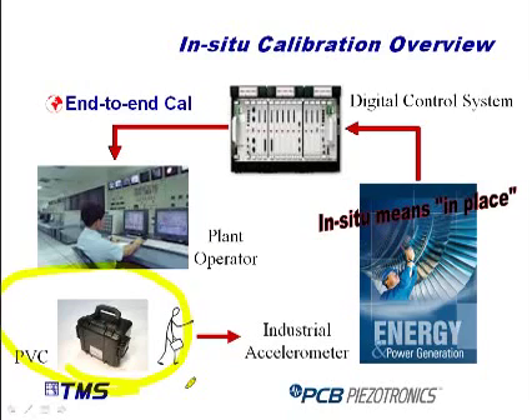In situ means in place. So we're going to where the transducer is installed on the power generation equipment, the turbine, engine, the machinery, the gears and pumps and heavy-duty industrial equipment that has the industrial accelerometers on them. And we calibrate the end-to-end entire measurement channel. So through the digital control system all the way back to the plant operator.